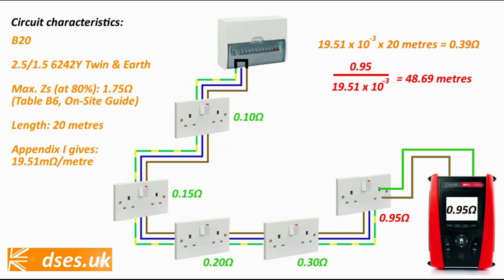We can of course open up the accessories we've identified on that circuit to check connections are tight, cores aren't fractured and sleeving isn't caught, all the things that cause this type of high reading. But what if that high reading remains after you've checked and verified every other point you can find? Maybe you shrug your shoulders as it's still a pass. We know the maximum rating for this circuit is 1.75 ohm for the B20 device protecting it, and so long as our external impedance in this case is below 0.8 ohm, then our endpoint reading of 0.95 ohm can be seen as being within tolerance.